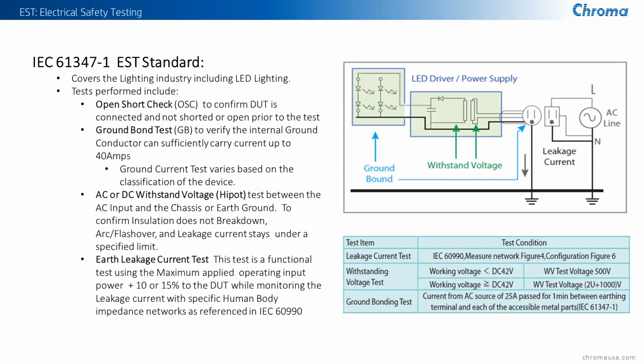61347-1 covers the lighting industry. This is just a brief coverage of that. Again, this one will give you requirements for ground bond, high pot, and earth leakage. And again, it has different levels of leakage current, and those are defined based on the IEC 60990 measurement network to identify based on the different human body impedance simulations.